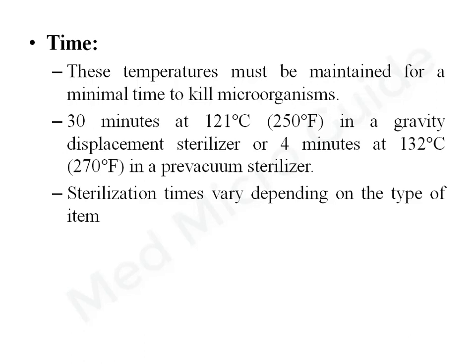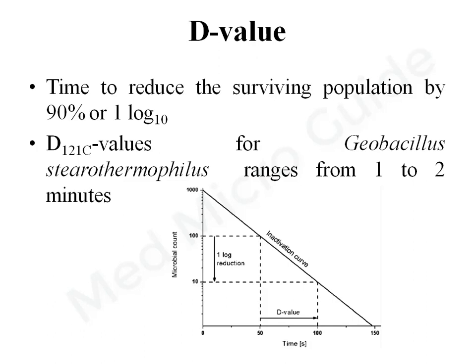Sterilization time varies depending upon the type of item, whether it is wrapped or unwrapped, and the type of sterilizer used. The D-value is the time required to reduce the surviving population of microorganisms by 90% or 1 log10. On this slope, the reduction of bacterial load from 100 to 10 takes place over a particular duration — that duration is the D-value. Geobacillus stearothermophilus, used to monitor steam sterilization, has a D-value ranging from 1 to 2 minutes at 121 degrees Celsius.